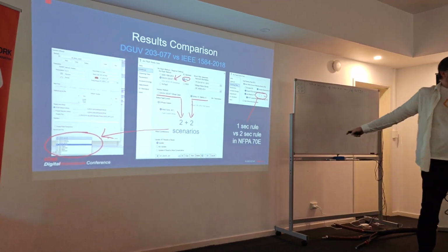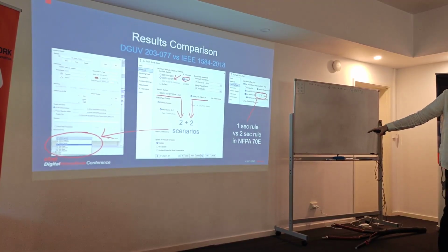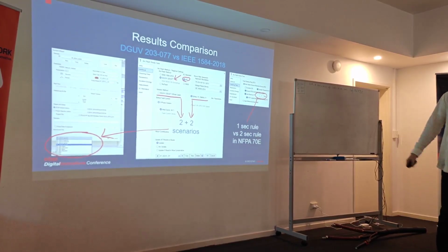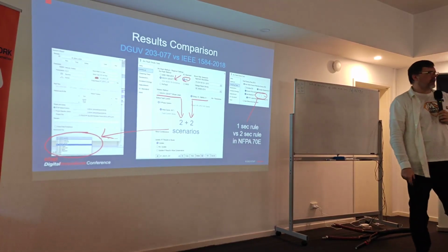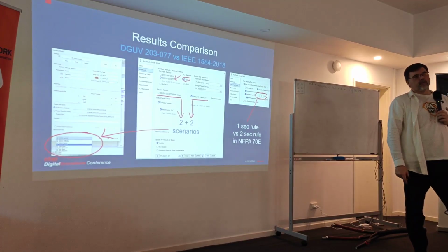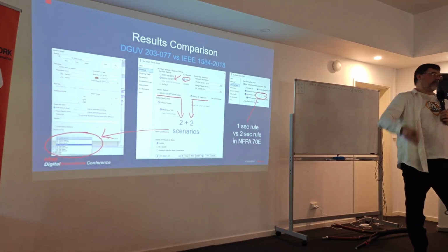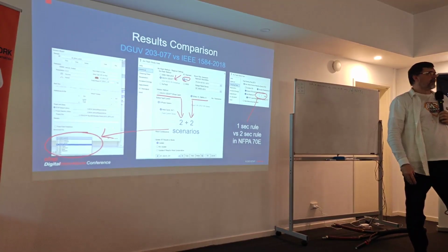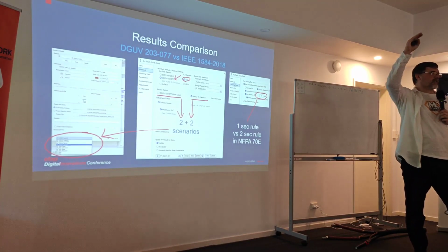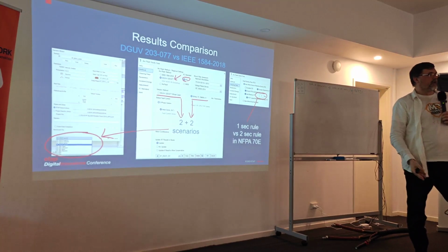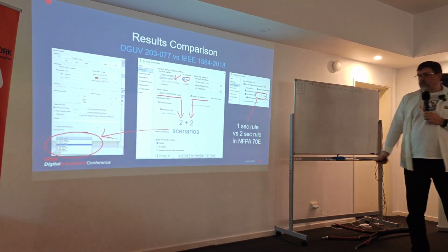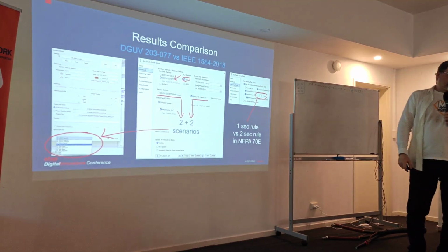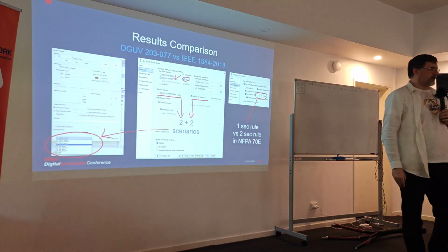Some of the companies will not allow you to use the 2 second rule, because they want to see the crazy energy. Crazy energy will give you the fast check that something is wrong with your protection. Because if you limit things to 2 seconds, you might be too positive and say, okay, it's like 40 calories. Actually, it might not be 40, it might be that it would trip in 800 seconds, yeah? And you just start to see a few thousand calories or something, which is not fully true, but it's not the exposure for the human. 2 seconds is like the cap that you can keep as exposure for the human, but the overall energy might be much higher.